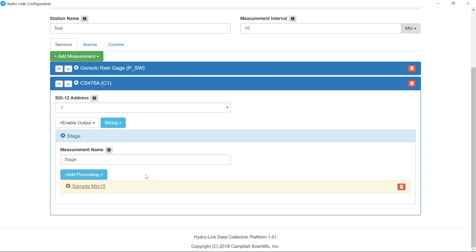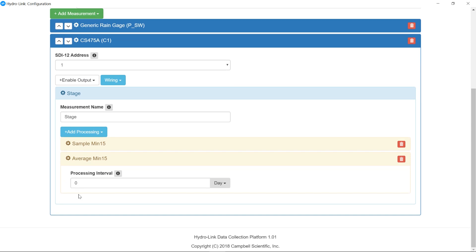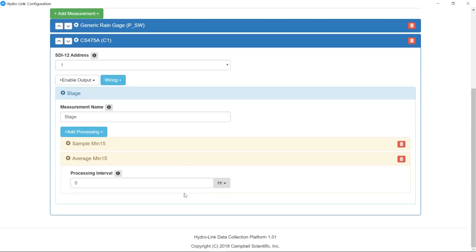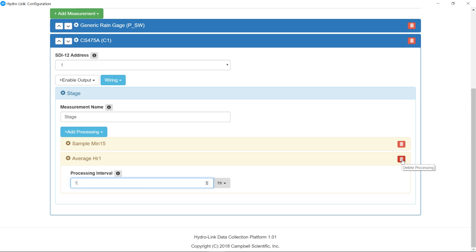Now this is a water level sensor. I could add in an average max or min. So for example, if I wanted to do an average, I would most likely change the rate here. So let's say I wanted to do an hour and set that to a one hour rate. Now what I'm going to get is four 15 minute values averaged and reported once an hour. So four 15 minute values averaged and stored in once an hour. If I don't want to do that, which is the case here, I'm going to come over here and just delete that.